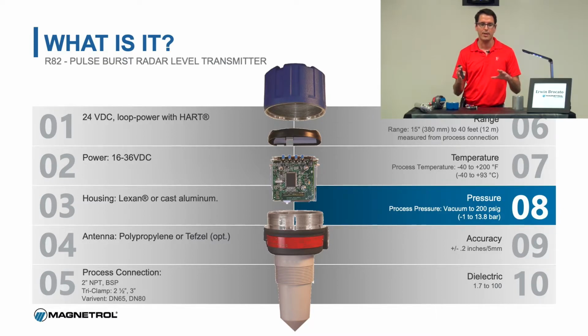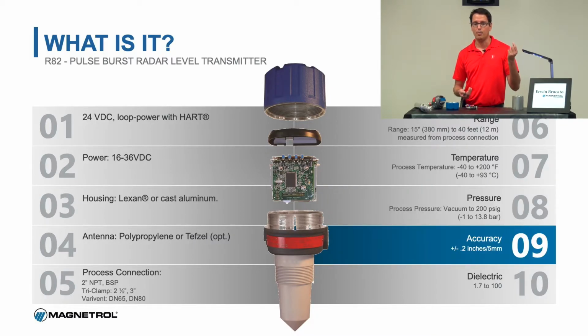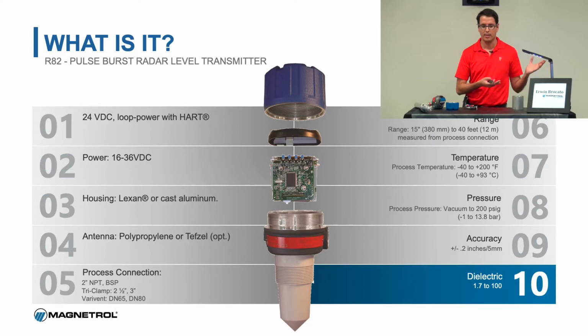So this is a very simple, low cost device for simple applications. Accuracy is still pretty good at 5 millimeters. And of course, with the dielectric constants, we can hit even very, very low dielectrics with this particular device. So if you're measuring some kind of low conductivity product, like an oil or some kind of hydrocarbon, it still has the performance of the higher end models, but it's just a more limited scope of what it can do.